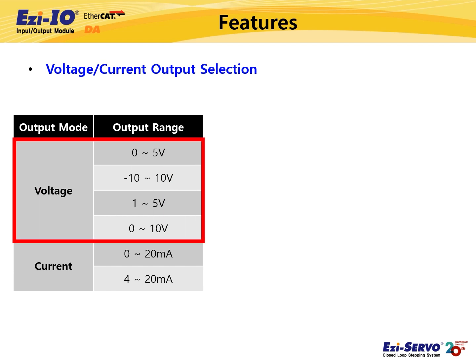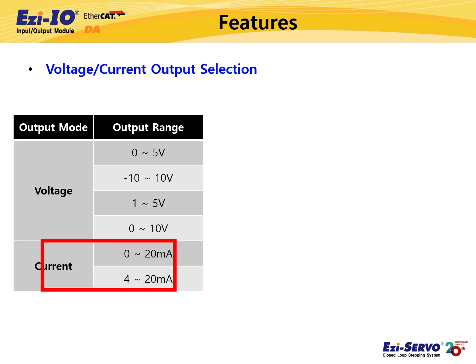Ezi-IO EtherCAT-DA also supports various voltage or current output modes — six output modes in total. For voltage output mode, there are four settings: 0 to 5 volts, minus 10 to 10 volts, 1 to 5 volts, and 0 to 10 volts. For current output mode, the output ranges are 0 to 20 milliamperes and 4 to 20 milliamperes.